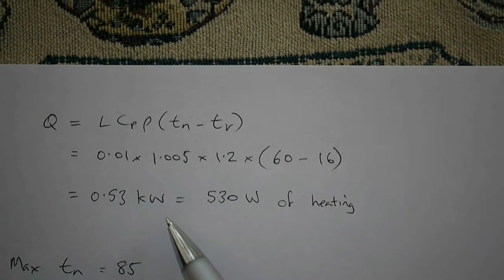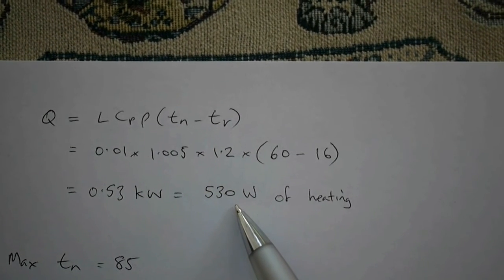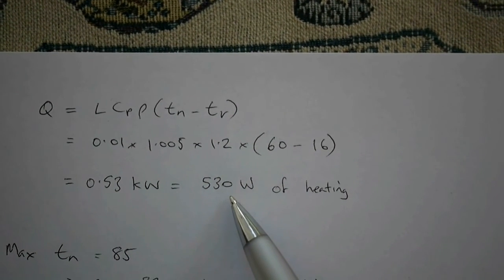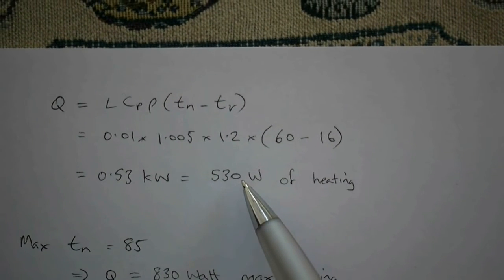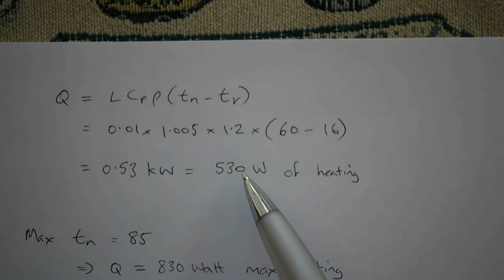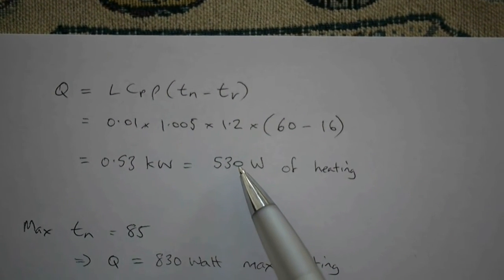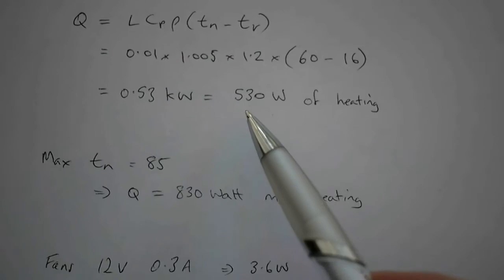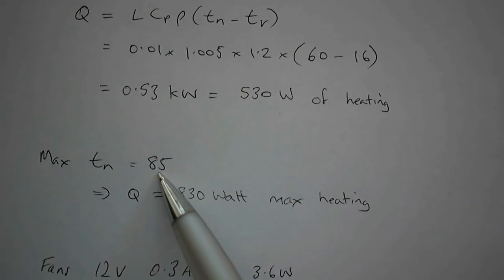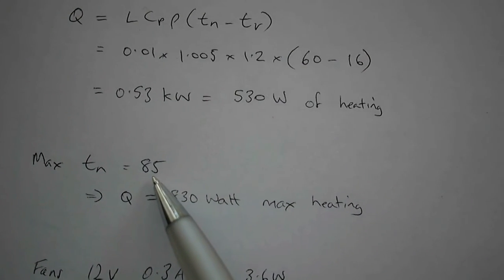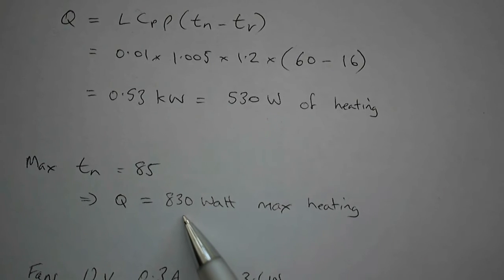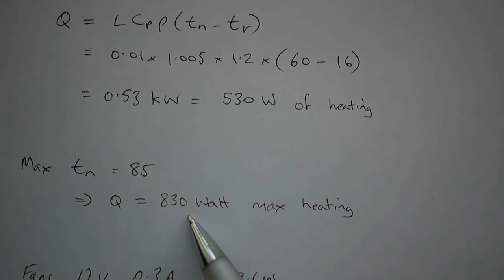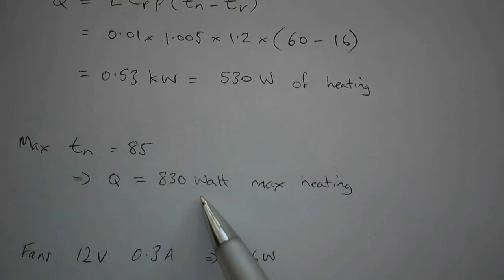That corresponds to 530 watts of heating when we're generating 60 degrees of temperature from the unit. The maximum I've ever seen is 85 degrees, so that would be about 830 watts as the maximum amount of heating we could get out of the unit.